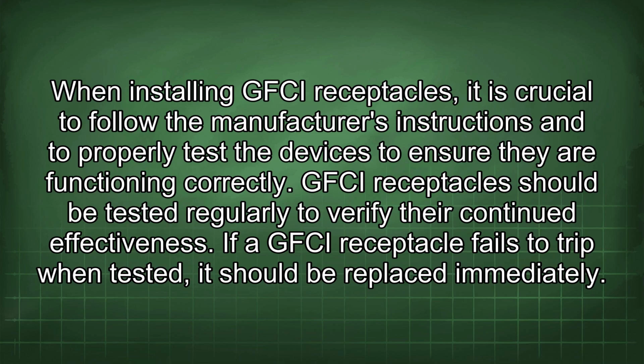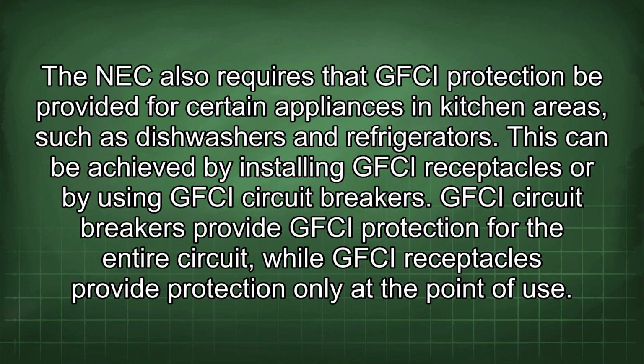When installing GFCI receptacles, it is crucial to follow the manufacturer's instructions and to properly test the devices to ensure they are functioning correctly. GFCI receptacles should be tested regularly to verify their continued effectiveness. If a GFCI receptacle fails to trip when tested, it should be replaced immediately. The NEC also requires that GFCI protection be provided for certain appliances in kitchen areas, such as dishwashers and refrigerators. This can be achieved by installing GFCI receptacles or by using GFCI circuit breakers.